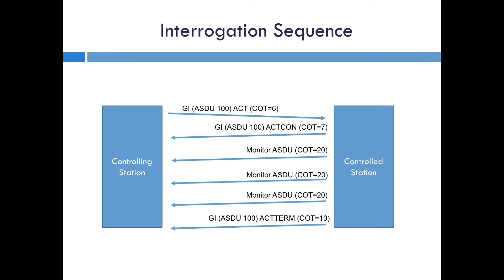Let's take a look at a typical interrogation sequence. Here we can see the controlling station sending a GI — ASDU 100 — with an ACT, or a COT, or cause of transmission of six. The controlled station responds with an ACT-CON which is a cause of transmission of seven. It then sends the monitor data — multiple monitored ASDUs in response to the GI, each of which has a COT or cause of transmission of 20. Then it wraps up the general interrogation sequence by sending an ACT-TERM, or a COT of 10.